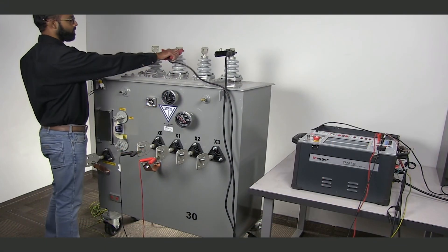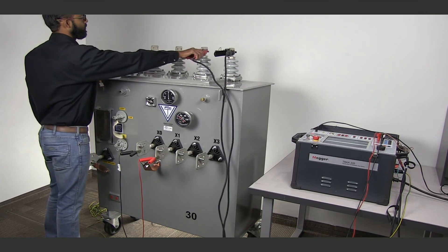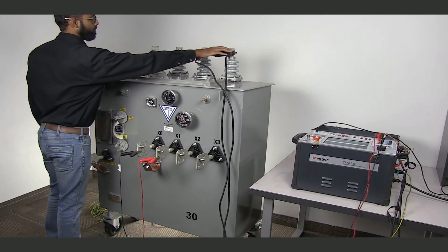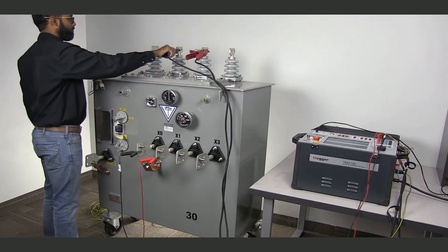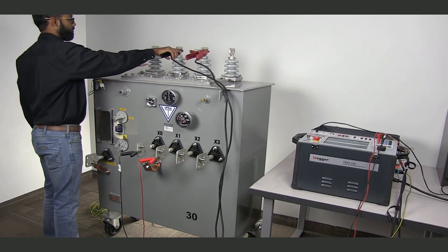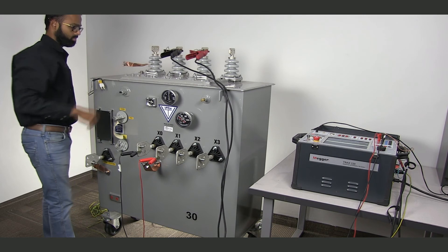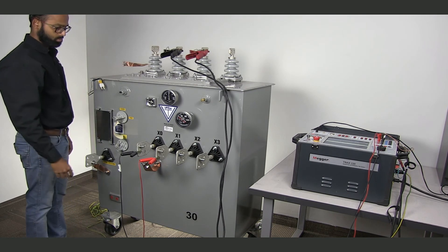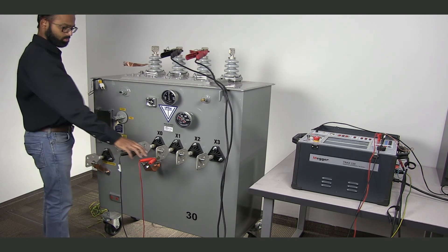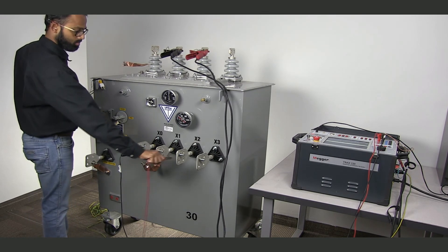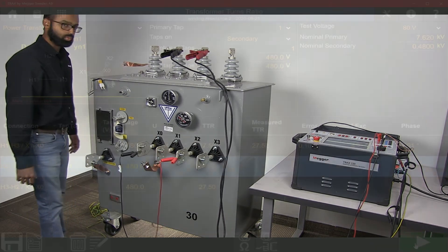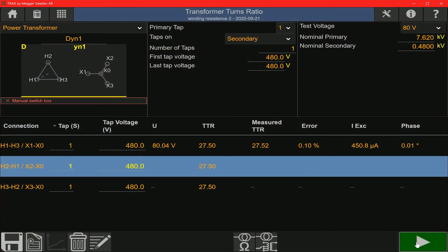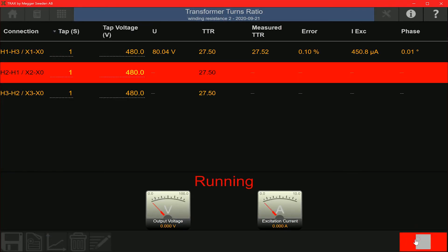To test the B phase, the Kelvin cables are connected on the H2 and H1 bushings. And the red sense cable is moved from the X1 bushing to the X2 bushing. Having changed the connections on the transformer, I'm going to run the measurement on the B phase.